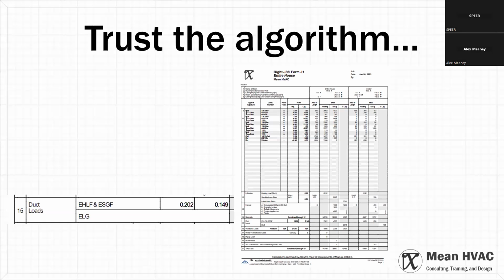If this number is very high and your ductwork doesn't seem like it should have a whole lot of load—say you're using R8 and a very well sealed duct—you're still going to get 20% plus in a lot of situations in a hot attic in Texas. Probably not too much higher than that for a well insulated, well sealed duct system.